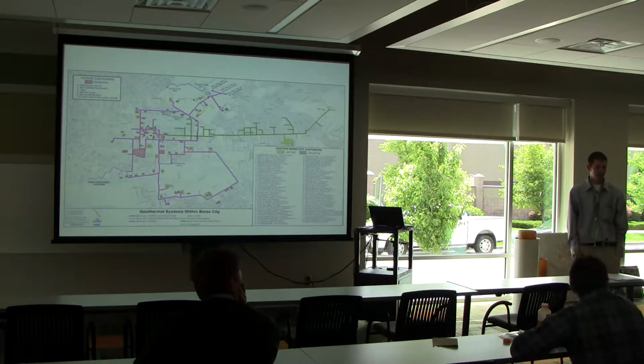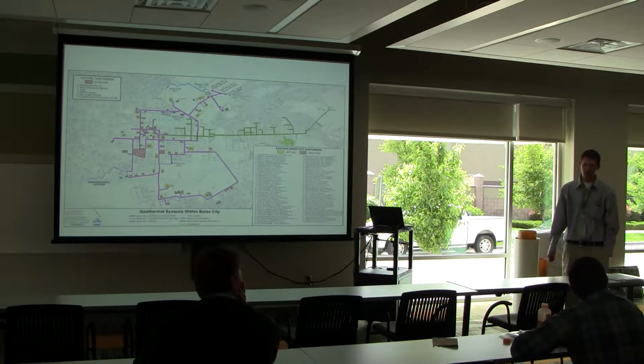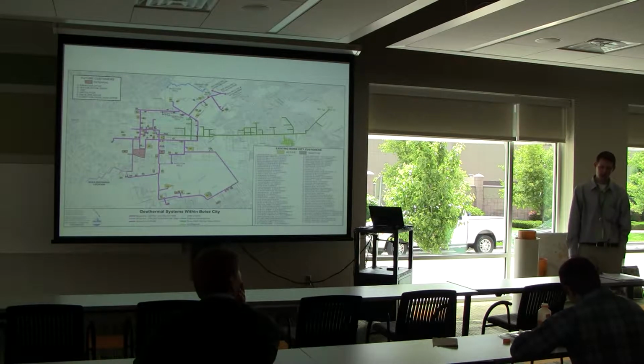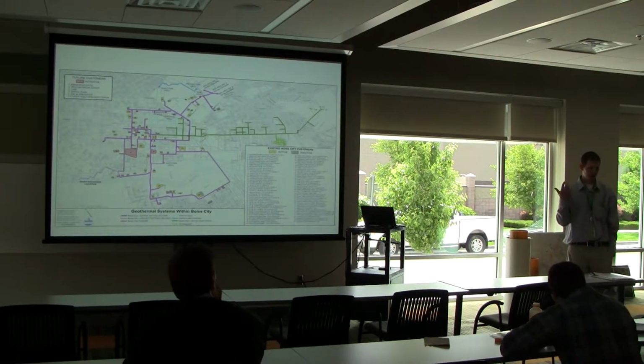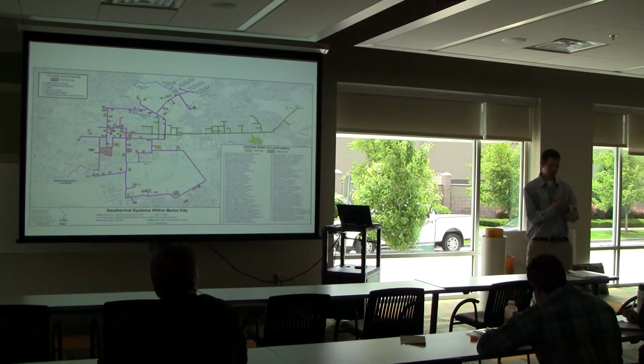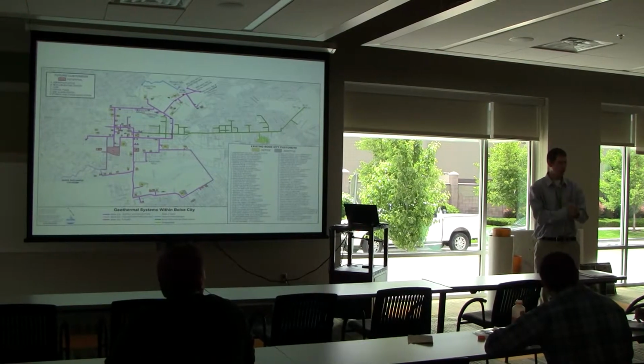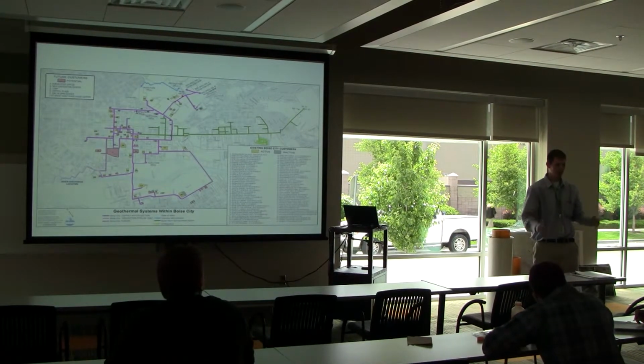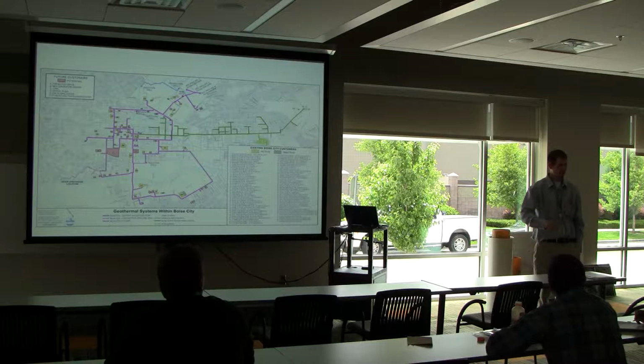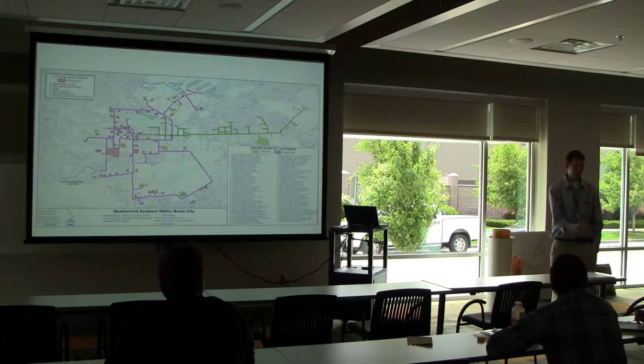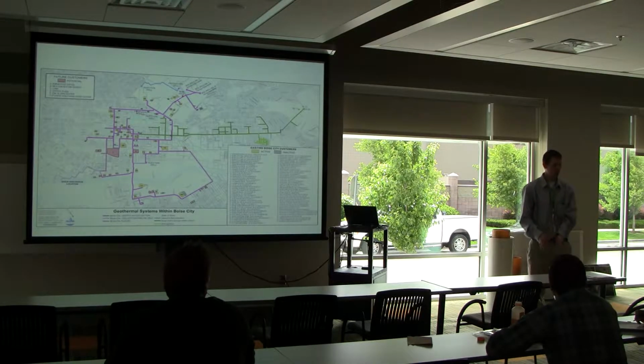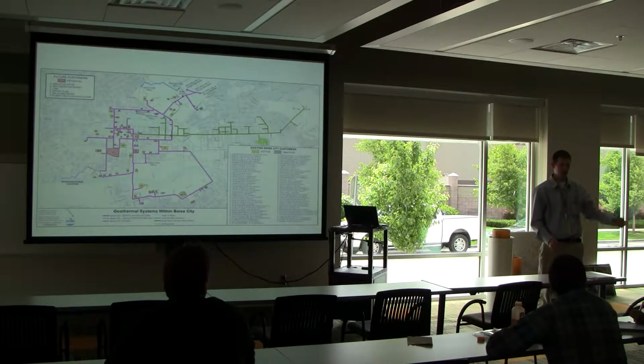If they're not pulling any heat off it in the summer, why are they disposing? Well, only a handful of them are billed by the gallon. It turns out the way Warm Springs Water District bills is by the orifice size. So you buy a house on Warm Springs Avenue for $100 a month, here's your orifice, and as much water as you can get through there, you can have it any time of the year. A lot of these houses don't have control valves, so this water flows into the building—sometimes to the heat exchangers, sometimes bypassing the heat exchanger entirely and going to disposal.